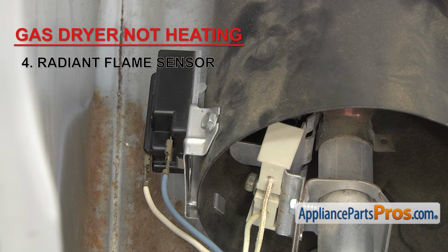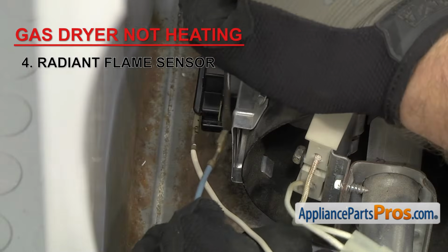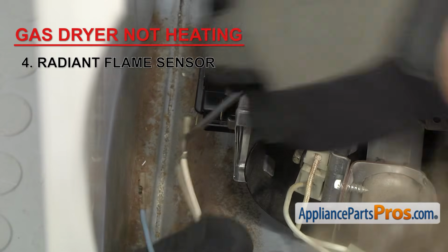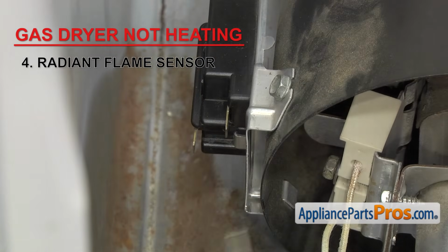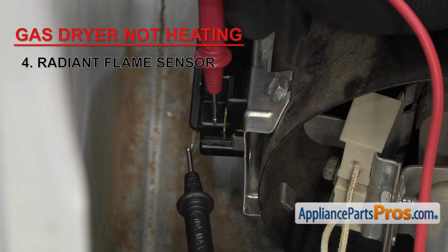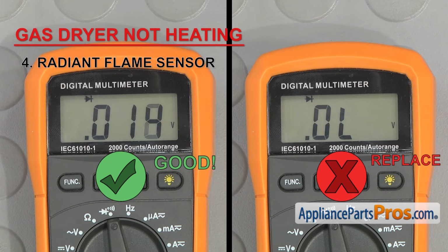To check it, we need to have our meter set to continuity, remove the wires from the part, and touch a probe to each terminal. If the part shows no continuity, or the igniter stays on all the time and the gas valve doesn't open, it'll need to be replaced.